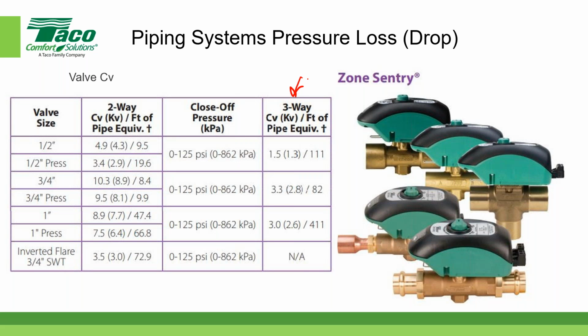And then another question: if the flow is 10.3, we show that for the 3/4 inch one as 1 psi. Why is it not 1 times 2.31? How do we get to 8.4 equivalent feet? Oh, because the 8.4 is equivalent length of pipe. Right. It's not equivalent feet of pressure drop.